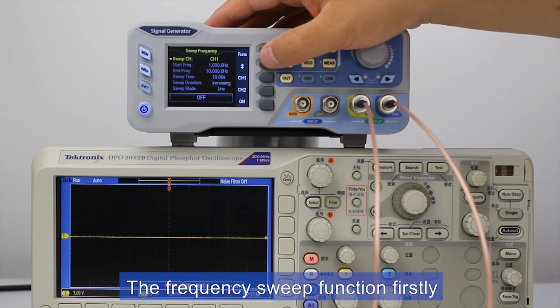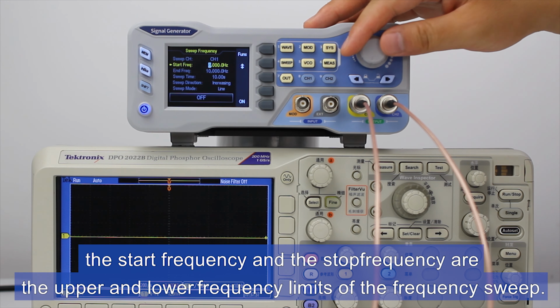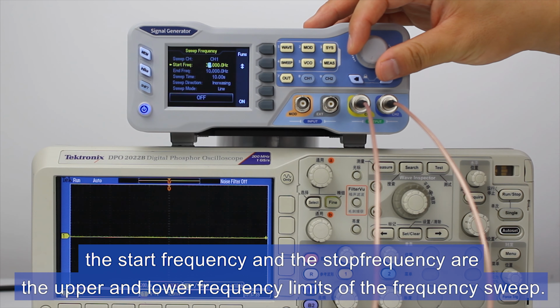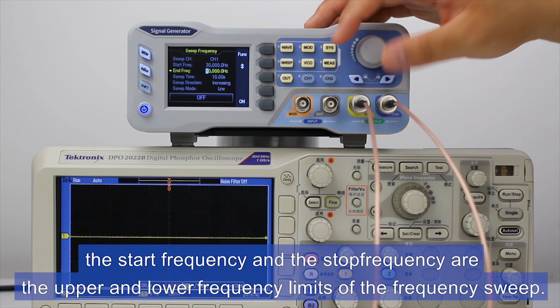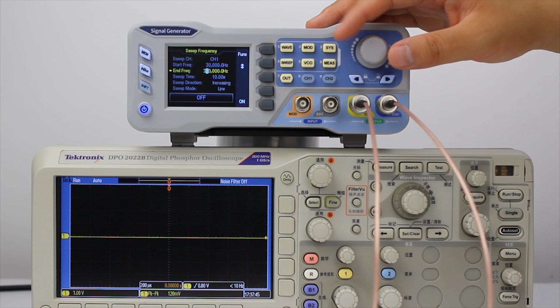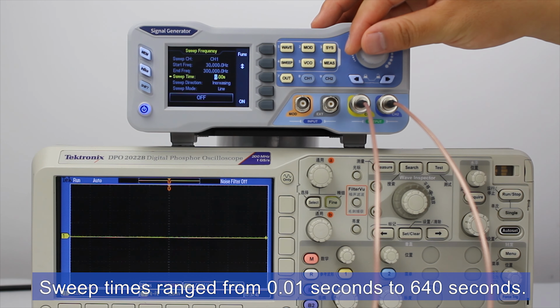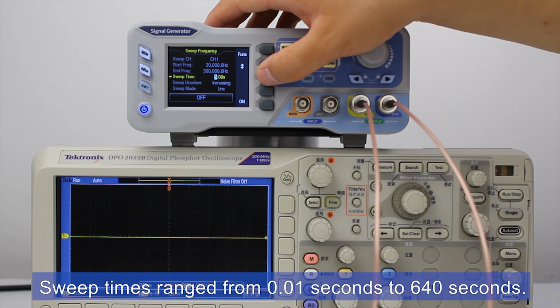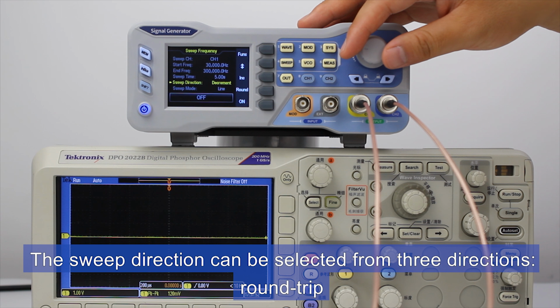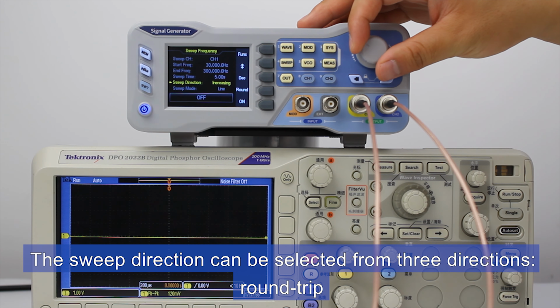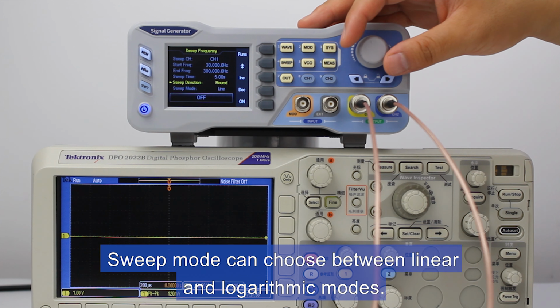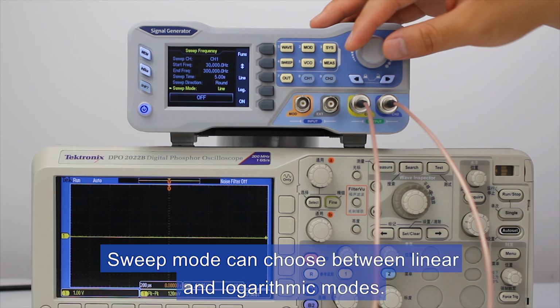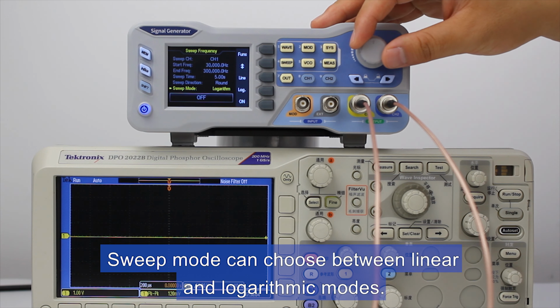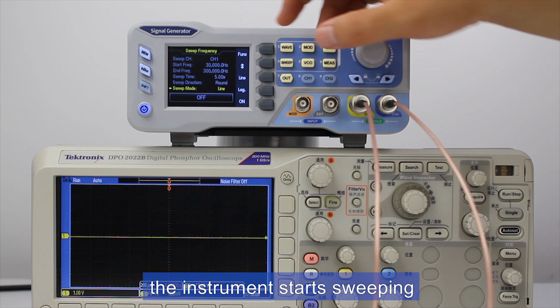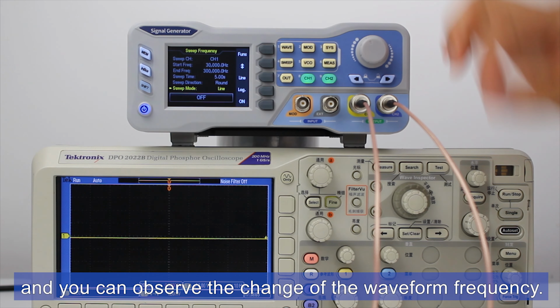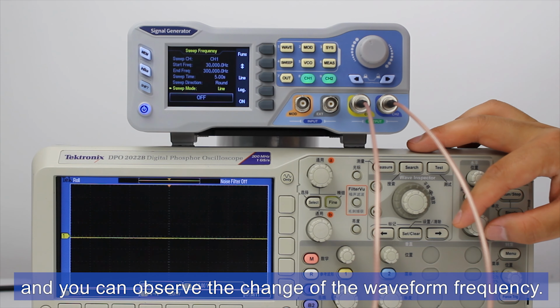The frequency sweep function. Firstly, the start frequency and the stop frequency are the upper and lower frequency limits of the frequency sweep. Sweep time ranges from 0.01 seconds to 640 seconds. The sweep direction can be selected from 3 directions: round trip, increasing and decreasing. Sweep mode can choose between linear and logarithmic modes. Press the on soft key. The instrument starts sweeping, and you can observe the change of the waveform frequency.